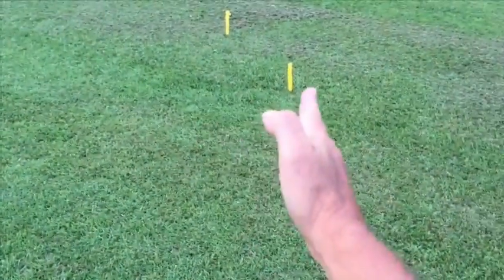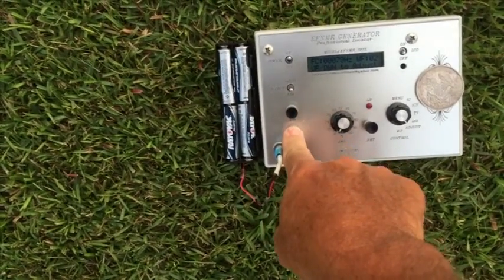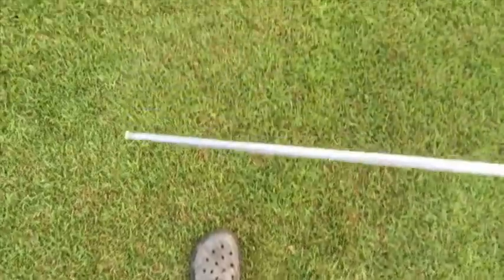Line yourself up with your generator, make sure you're still okay. Put a line down, a mark at your heel. Now you can see that your frequency is off — it started moving to the right. The line moved to the right. I went up three hertz. If I go down three hertz, the opposite will happen.